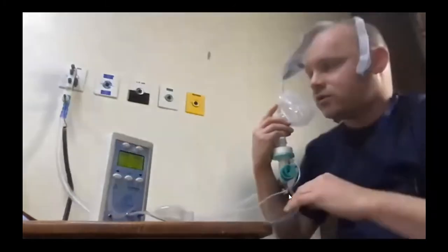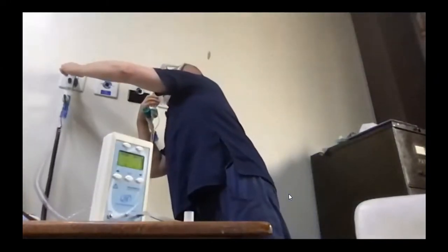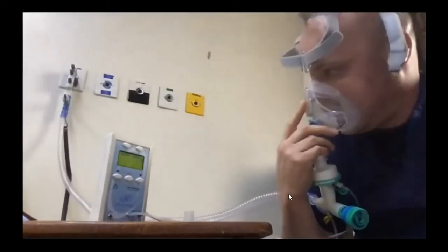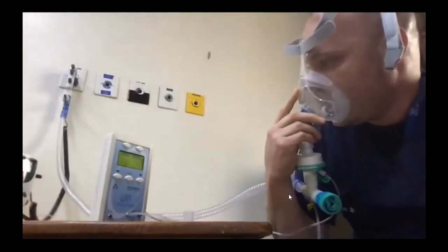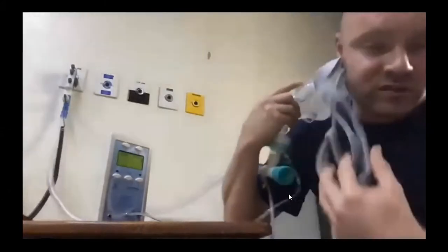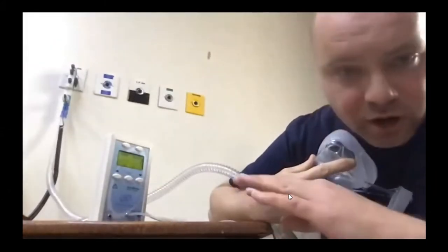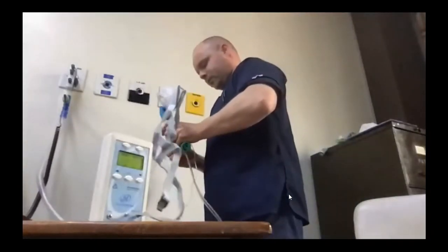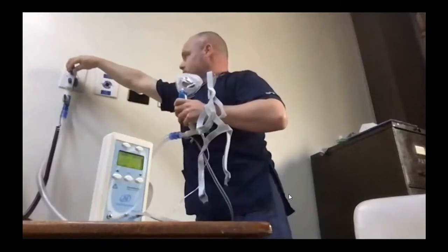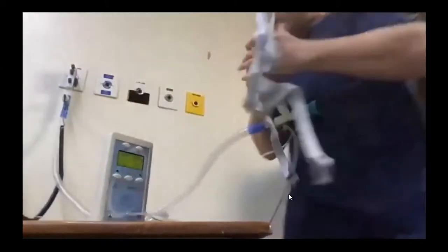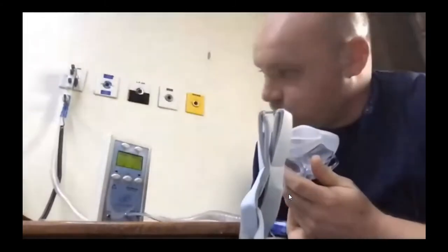If I go through another 360-degree turn, so the measured flow there is sitting at just under 40 liters per minute. My oxygen-enriched mixture is still closed completely, but what you'll find is the bottom end of this device is around 30% to 32% with the O2 entrainment, the O2 enrichment knob, turned off completely. And if I go through another half a turn, we now jump up to just over 50 liters per minute.